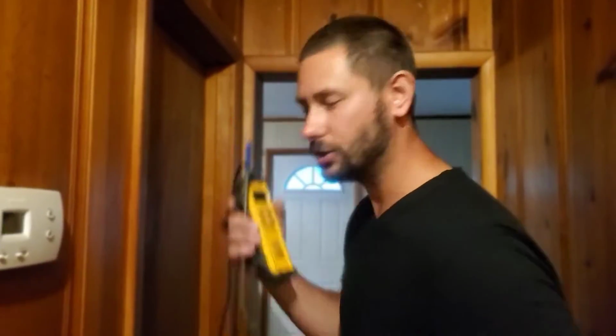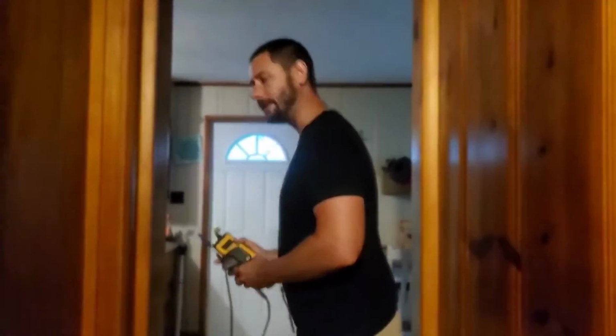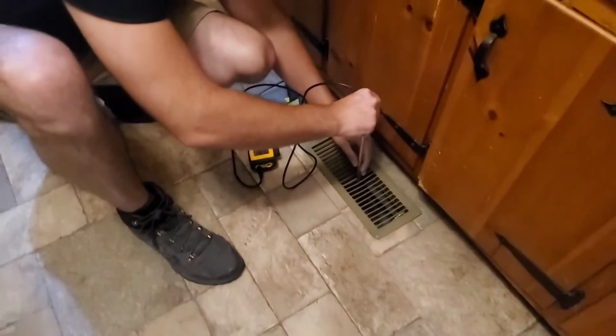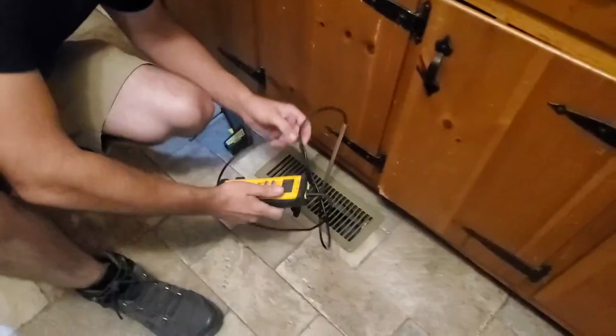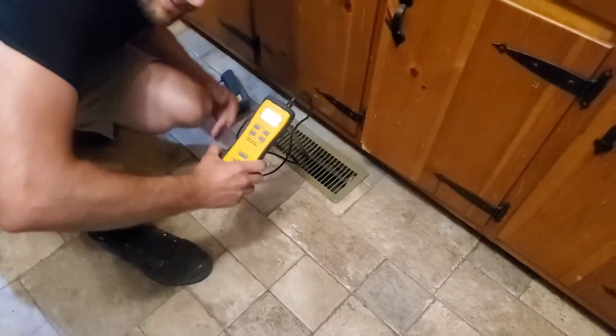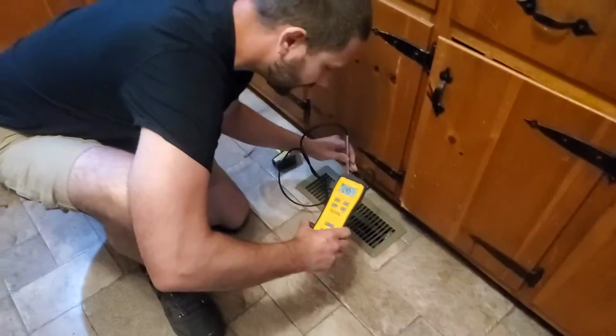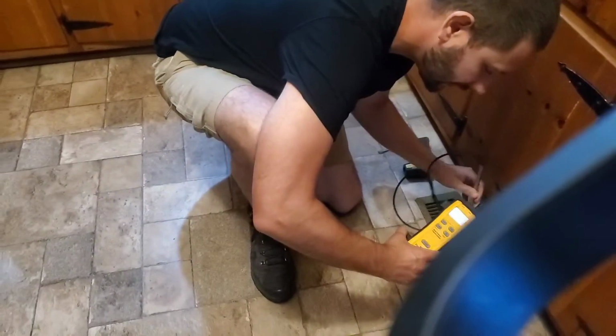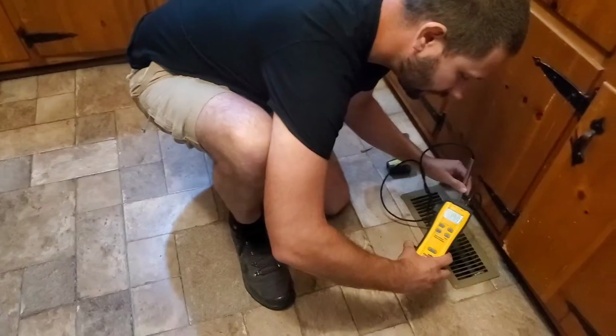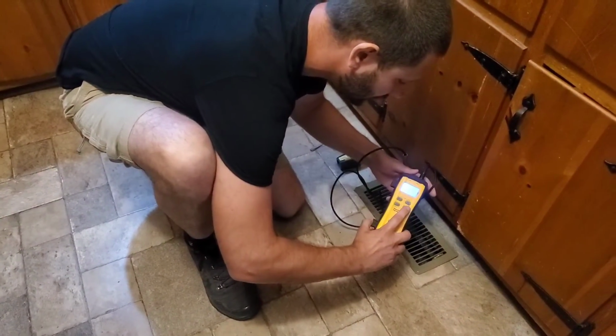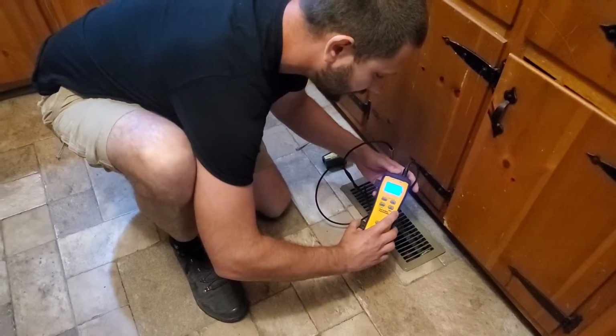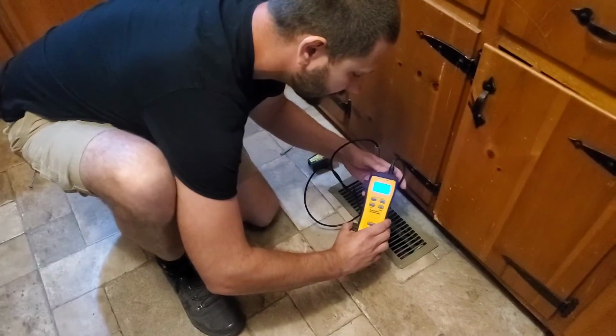Let's go check this out real quick - 71 on the inside temperature. Now come over here - this is a very expensive one, a dual input psychrometer, but you don't have to use one of these. The temperature probe is in the vent, and if you zoom in you can see it reads 53 degrees.